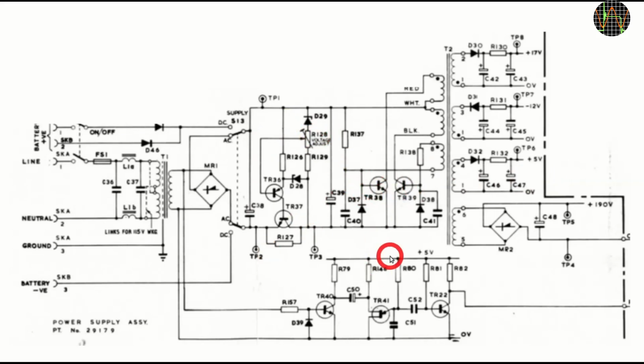There is an additional circuit that takes the AC from the mains transformer and converts the mains frequency into pulses to sync the analog to digital conversion. Obviously, that part does nothing when running on DC, but when running from AC, it makes sure that the integration period is synced to mains, which is a standard way of reducing the effect of mains noise in the measurements.